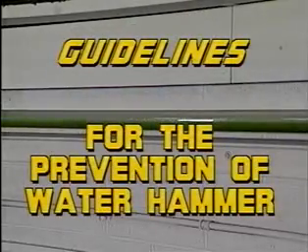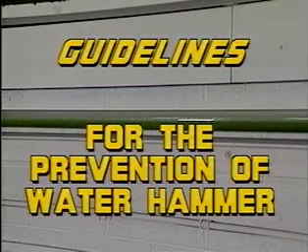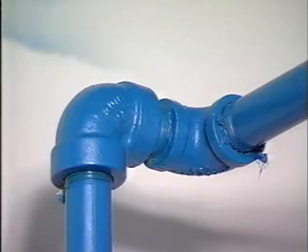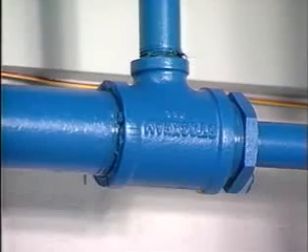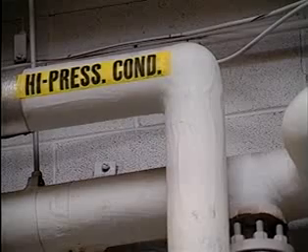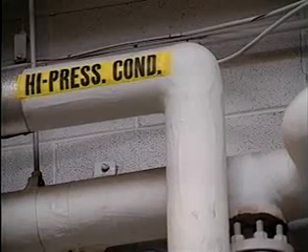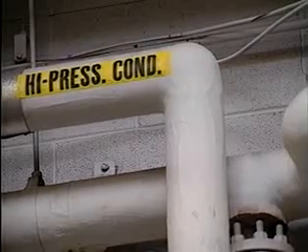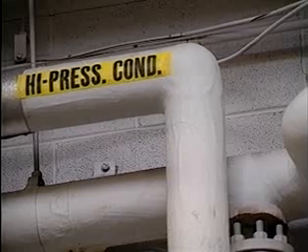Water hammer begins when some force accelerates a column of water along an enclosed path. The incompressible nature of water gives it the power of a steel sledge as it slams into elbows, tees, and valves. The resulting vibrations are transmitted along the water column and piping, damaging fittings and equipment far removed from the problem source.